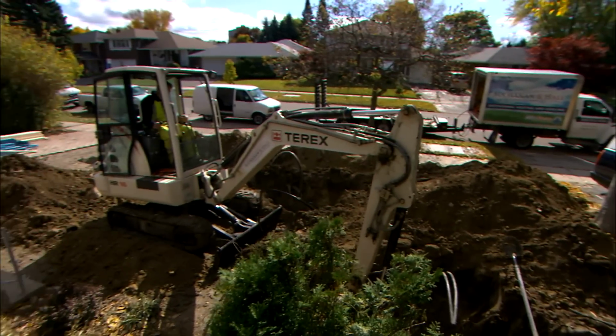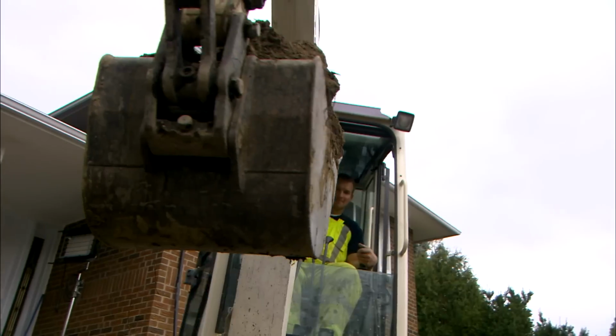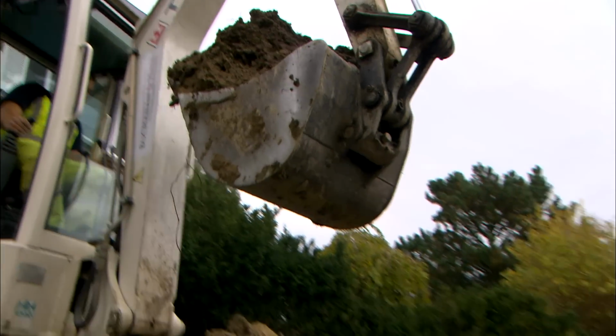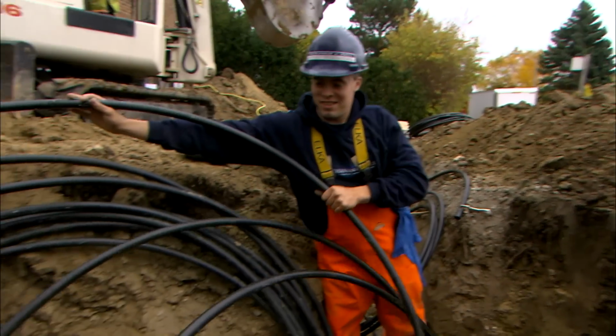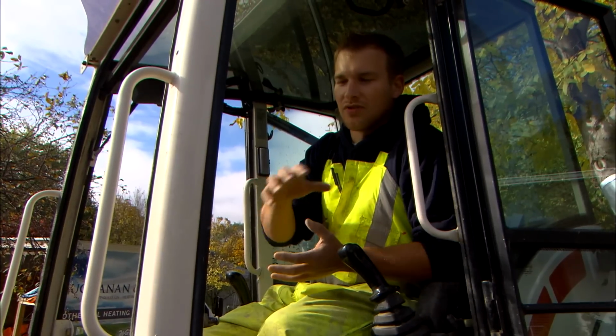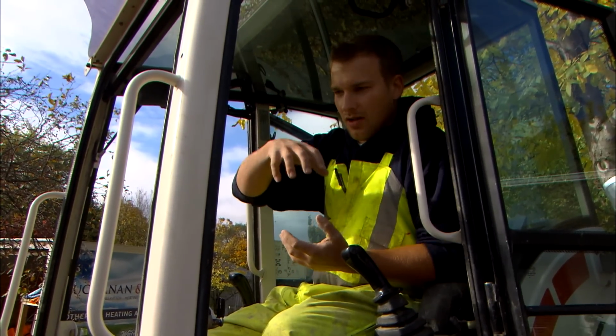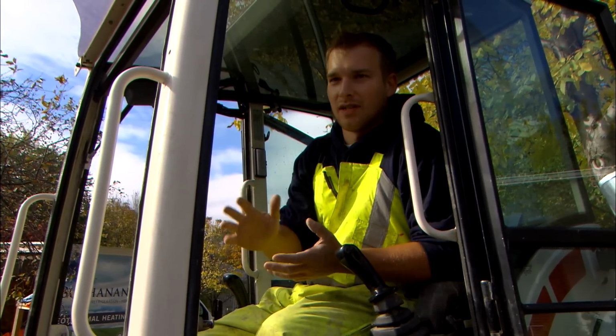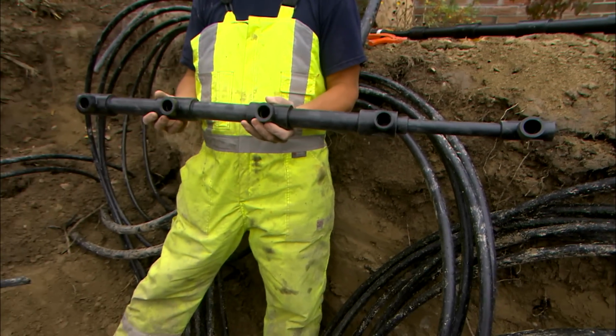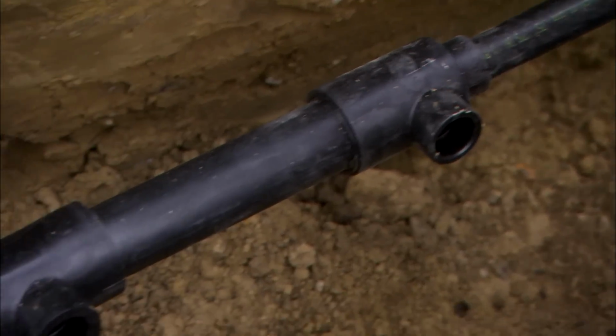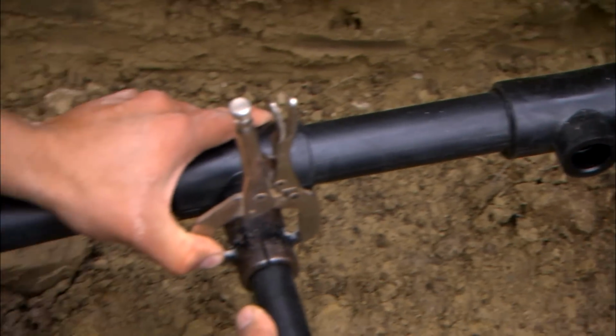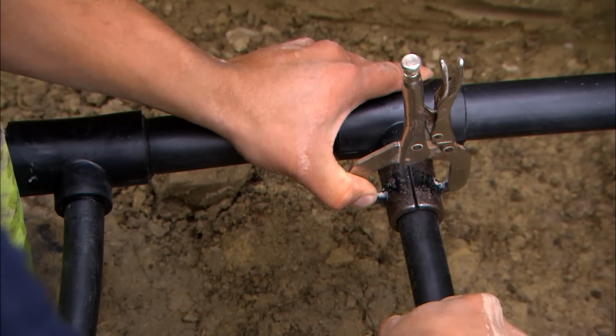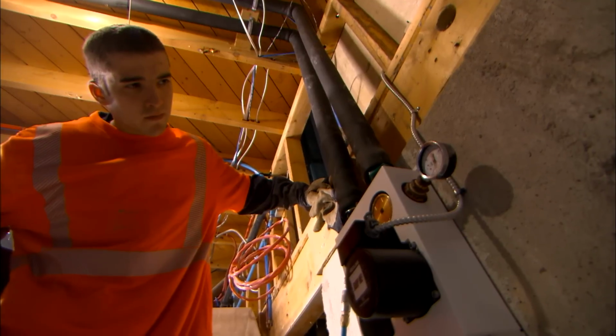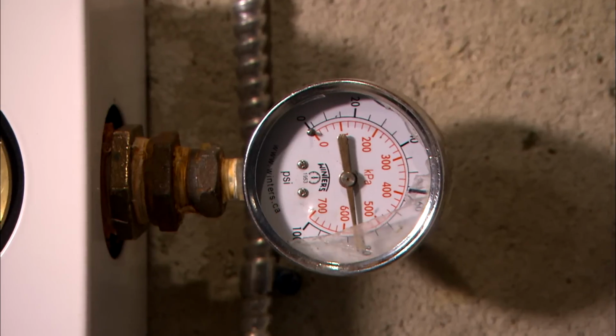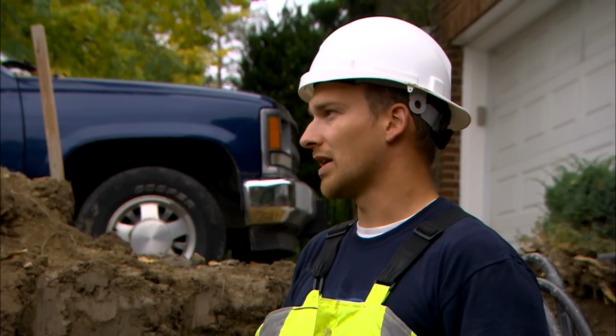Today we're going to dig up all of the vertical bores, bring them back, and manifold them all together, which will distribute the water solution throughout all of the pipes equally. We need to fuse all of these into this manifold, put some pressure on it to make sure it's good. We'll hook a compressor up at the machine and pressure it all up, then backfill once we've tested it.